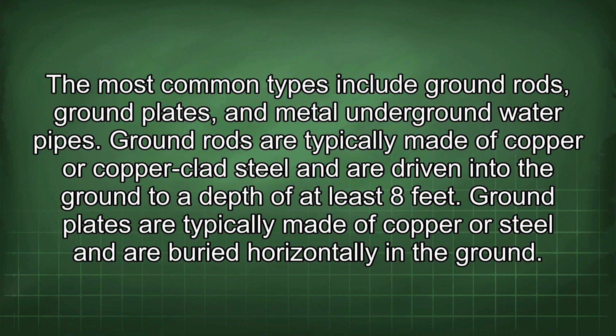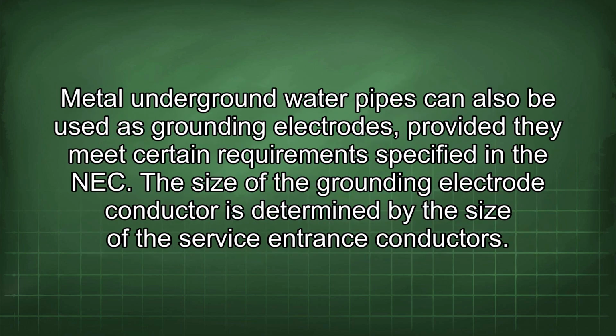The most common types include ground rods, ground plates, and metal underground water pipes. Ground rods are typically made of copper or copper-clad steel and are driven into the ground to a depth of at least 8 feet. Ground plates are typically made of copper or steel and are buried horizontally in the ground. Metal underground water pipes can also be used as grounding electrodes, provided they meet certain requirements specified in the NEC.